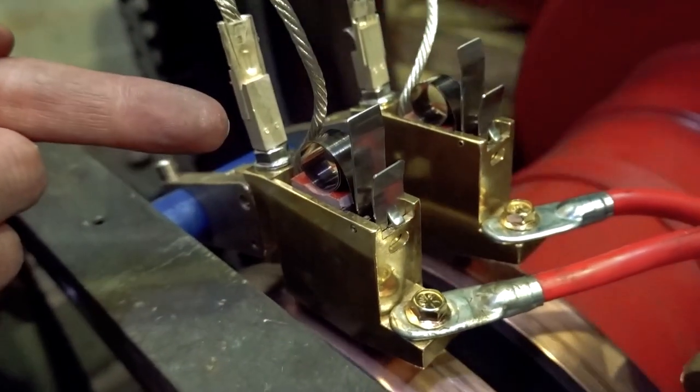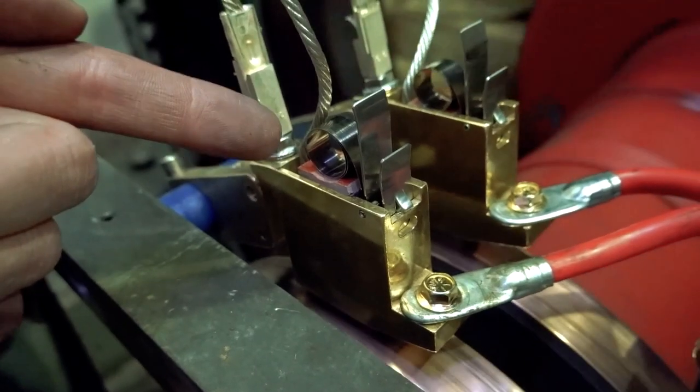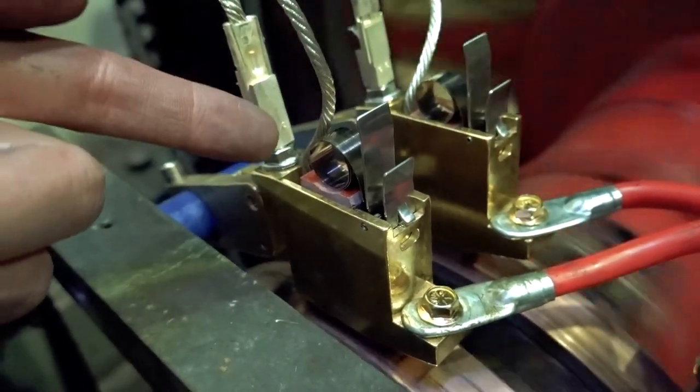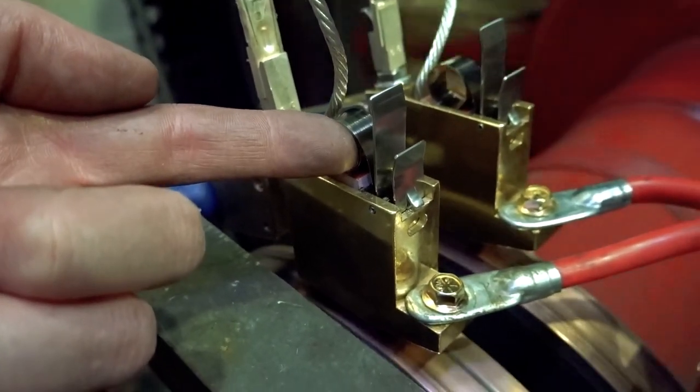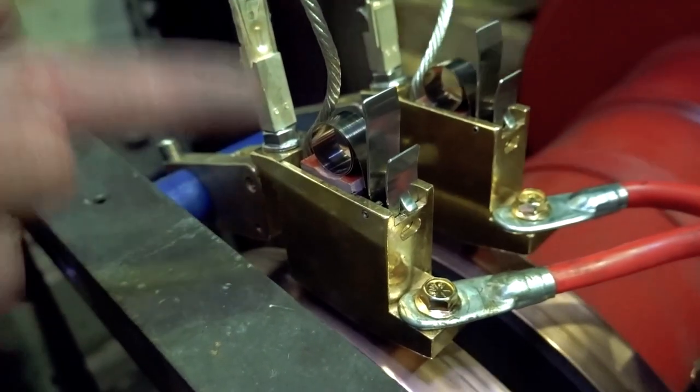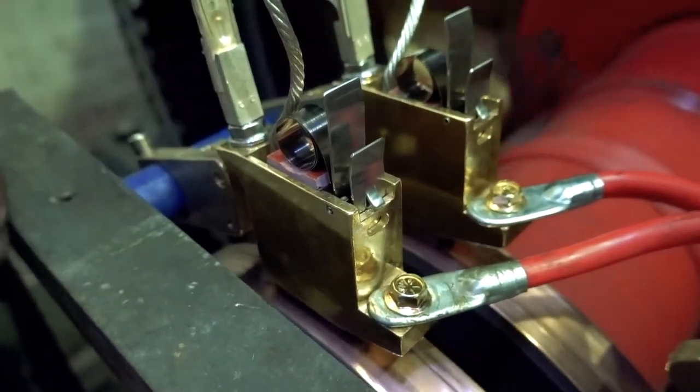So by having the intentional mismatch, the intentional oscillation, it causes the brushes to oscillate in their holders and they don't get gummed up and stuck in place. So we're just exercising this little spring a little bit and they just work. Yeah, keeping the debris out of the holder.